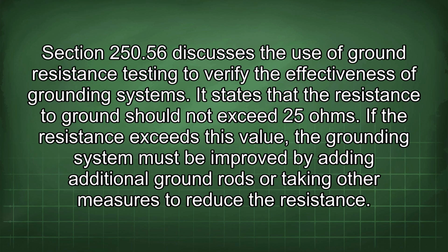Section 250.56 discusses the use of ground resistance testing to verify the effectiveness of grounding systems. It states that the resistance to ground should not exceed 25 ohms.